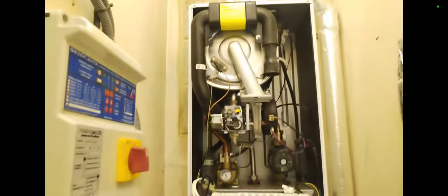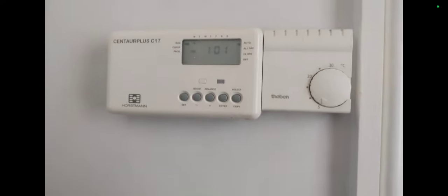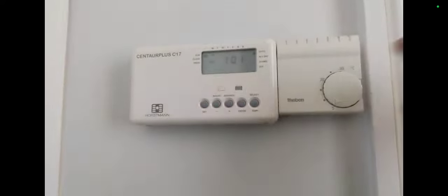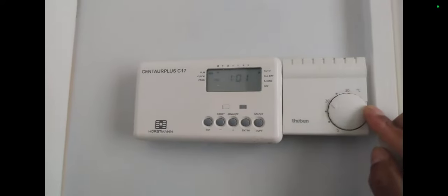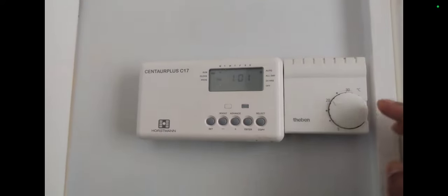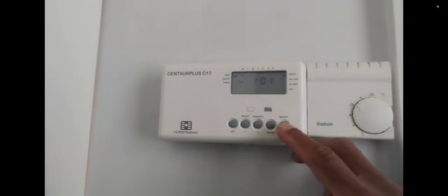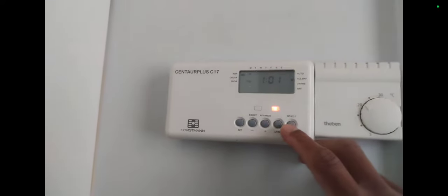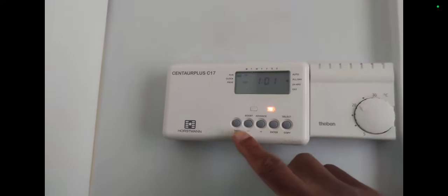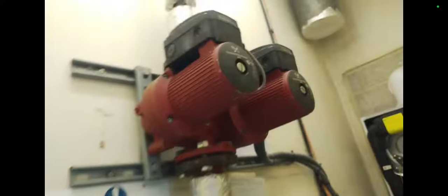And some pumps. There's a room sealed boiler. I had to go to the room stat in this building and get it to kick in because there was no demand whatsoever. So I've got the unit to call for heat. Then the pumps came on. Finally kicked in, there's a capacitor there hiding.